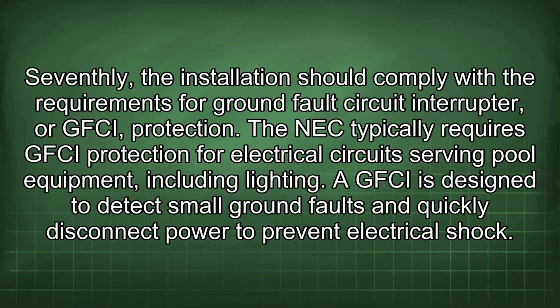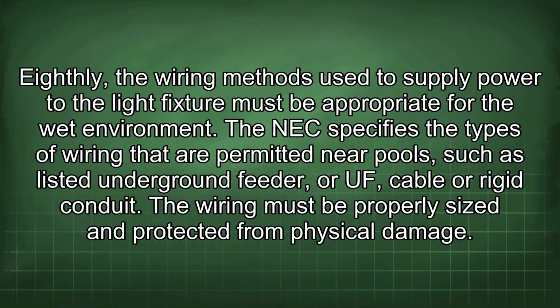Seventhly, the installation should comply with the requirements for ground fault circuit interrupter, or GFCI, protection. The NEC typically requires GFCI protection for electrical circuits serving pool equipment, including lighting. A GFCI is designed to detect small ground faults and quickly disconnect power to prevent electrical shock. Eighthly, the wiring methods used to supply power to the light fixture must be appropriate for the wet environment. The NEC specifies the types of wiring that are permitted near pools, such as listed underground feeder, or UF, cable or rigid conduit. The wiring must be properly sized and protected from physical damage.